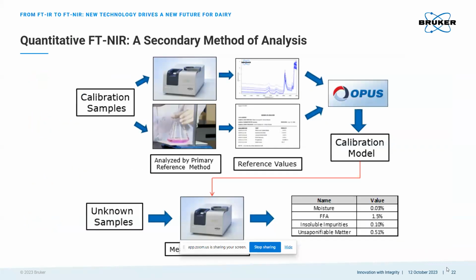So, how does NIR work in practice? For starters, NIR is a secondary method of analysis. So what this means is that it uses wet chemistry or another reference method to generate values. And ultimately, the NIR is only going to be as good as the wet chemistry that it's based upon. And the basic way this works is that a set of samples are run on NIR and their spectra are collected. These same samples are sent for wet chemistry, and those spectral files that we collected are assigned the wet chemistry value. So those two aspects are married together.